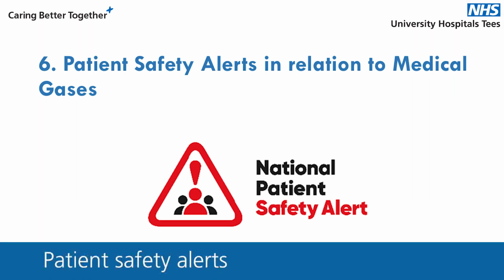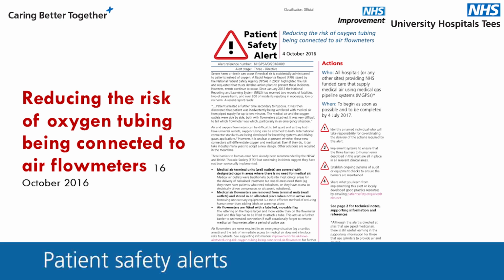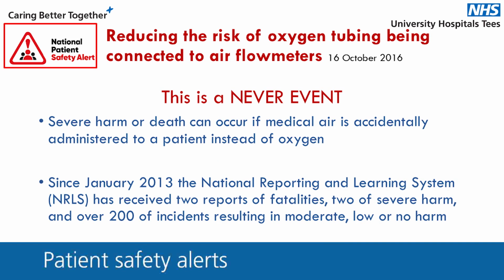National Patient Safety Alerts. There are 2 medical gas alerts specifically related to the use of oxygen. The first alert highlights the importance of checking that oxygen tubing has been connected to the correct oxygen flow meter and to ensure that established systems are in place to reduce the risk of connecting the oxygen tubing to an air flow meter. The accidental administration of air instead of oxygen to a patient is a never event. This can cause severe harm or even death. The recommendations of the National Safety Alert are aimed to decrease human error, but continuous vigilance is required.